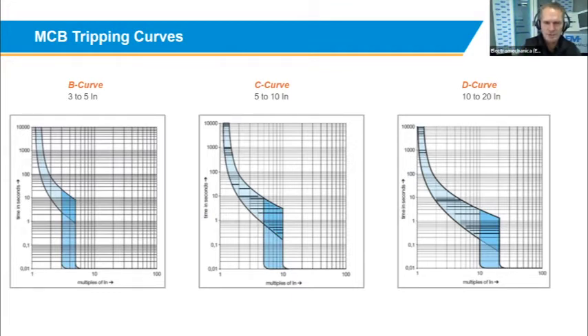If it is ICU equals ICS, you can then close it for a second time, and it will open for a third time and handle the 10,000 amps. If the breaker is rated 50% of ICU equals 50% of ICS, as I said, on the second close, third opening, it will only be able to handle 5,000 amps. So if the board is rated 10,000 amps, the fault level is 10,000 amps on your board, on the second close and the third opening, that product can explode and cause more damage inside the board.